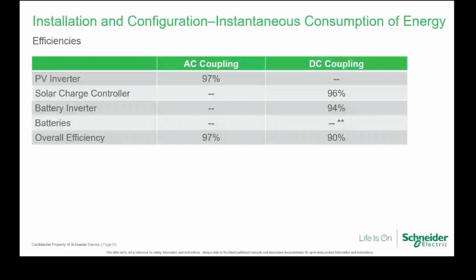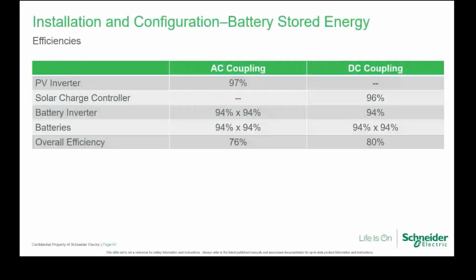However, when you take the batteries into account, if you need to charge your batteries from the AC side and then discharge later on, you're going to see that the overall efficiencies will be lower, because the battery inverter has to do two inputs and outputs, and then the batteries need to do input and output as well, charge and discharge. With a DC coupled solution, it actually comes up a little bit better than the AC coupled solution. That's if you have to use the batteries. If you're not using the batteries to power your loads in the middle of the day, then the AC coupling solution will be better. That's why people tend to use hybrid solutions, where we have both AC and DC coupling.